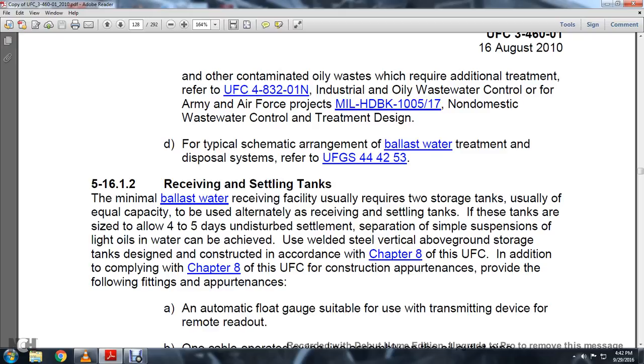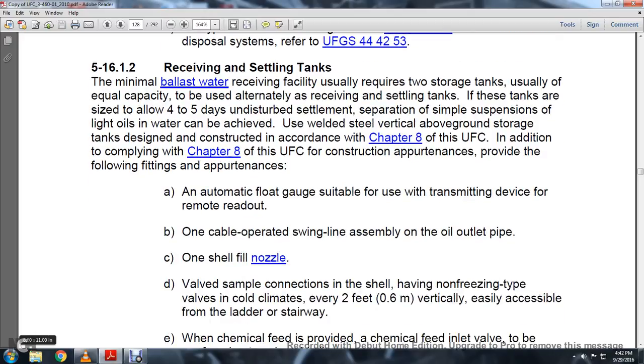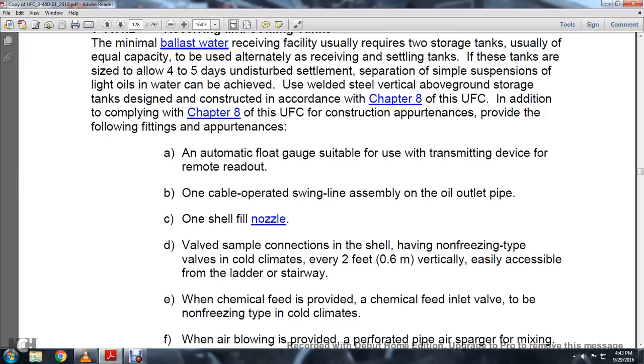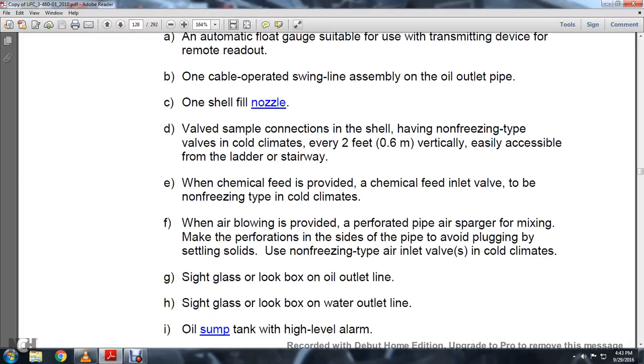Use a welded steel vertical aboveground storage tank designed and constructed in accordance with Chapter 8 of the UFC. In addition to complying with Chapter 8 of the UFC, provide the following fittings and provisions: an automatic float gauge suitable for use with a transmitting device with remote readout, one cable-operated swing-line assembly on the oil outlet pipe, one shell fill nozzle, valve sample connections on the shell, non-freeze type in cold climates, with valves every 2 feet vertically, easily accessible from the ladder or stairway. When chemical feeds are provided, use a chemical feed inlet valve of non-freezing type in cold climates.